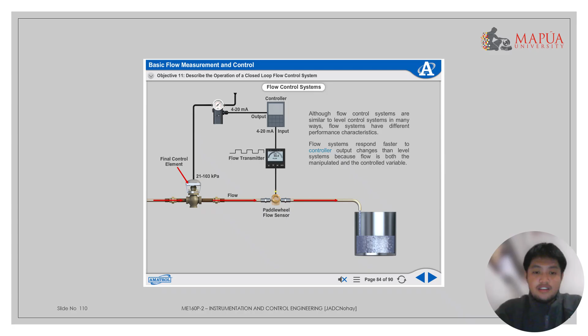Although flow control systems are similar to level control systems in many ways, flow systems have different performance characteristics. Flow systems respond faster to control output changes than level systems because flow is both the manipulated and the controlled variable. PI control for flow systems: the control method used most often in flow systems is the proportional plus integral mode. Flow control systems are subject to frequent load disturbances, so PI control allows these systems to react quickly to these disturbances.